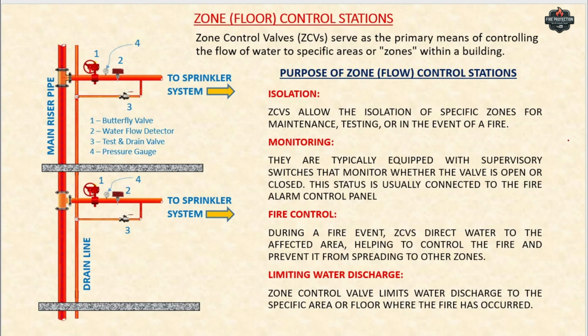According to NFPA 13, these control stations are required to cover areas not exceeding 50,000 square feet when dealing with light and ordinary hazard. Like, each floor area should be less than this 50,000. If more, you have to use 2 or 3 floor control stations.